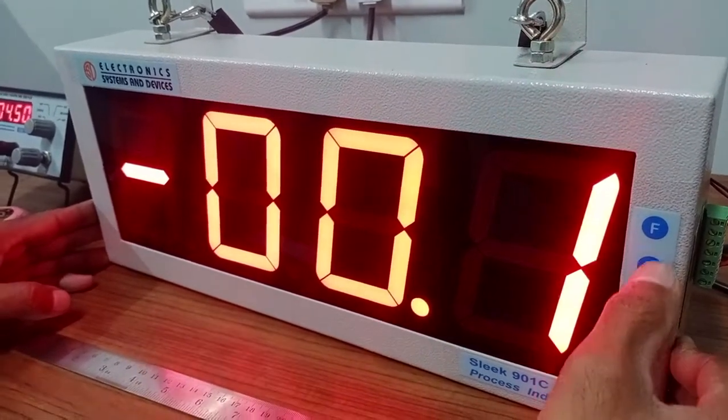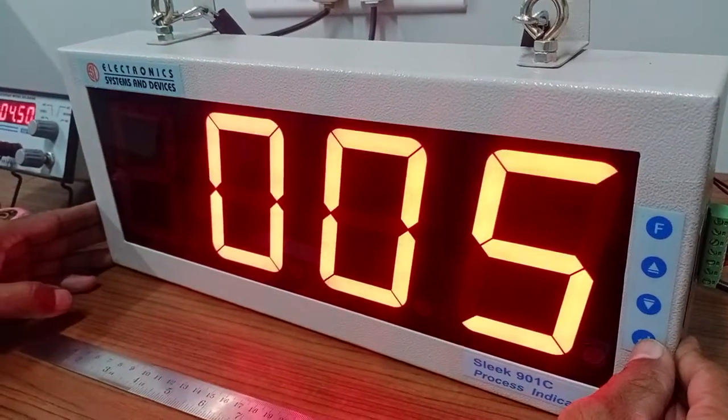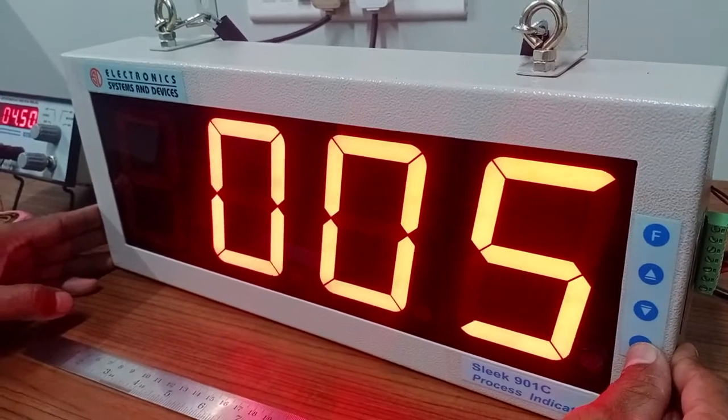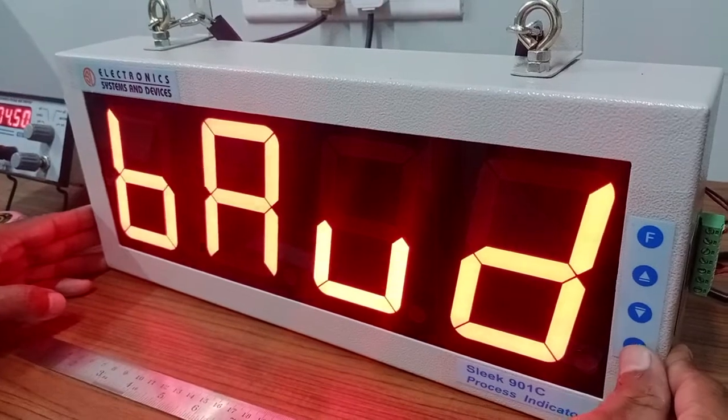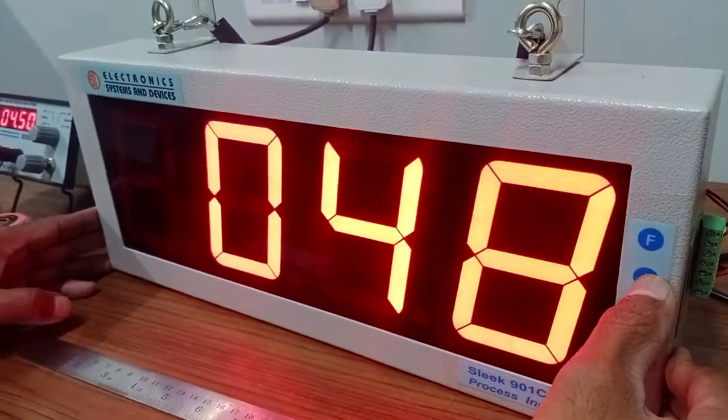Enter. Address - this is for Modbus RTU communication using RS485. This is the slave ID address. Enter. Baud rate is selectable from 1200, 2400, 9600, 4800. This one doesn't have communication, so we'll just skip it.